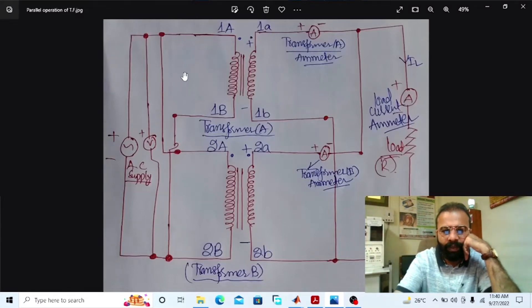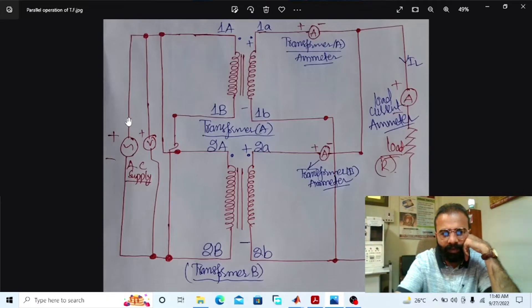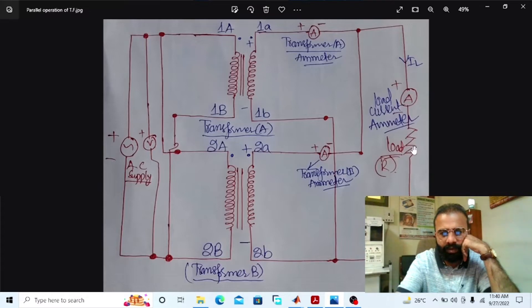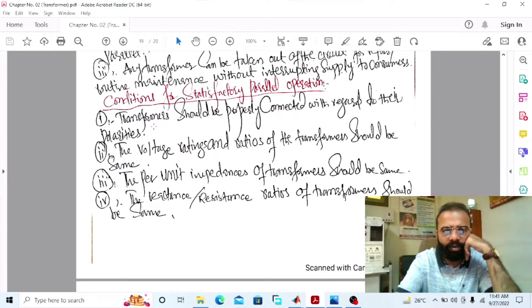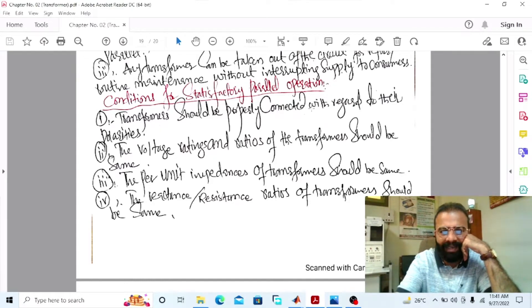The transformers are connected in parallel when the primary windings of both transformers are connected with the supply busbars, and the secondaries of both transformers are connected with the load busbars. The conditions for satisfactory parallel operation: the transformers should be properly connected with regard to their polarities.